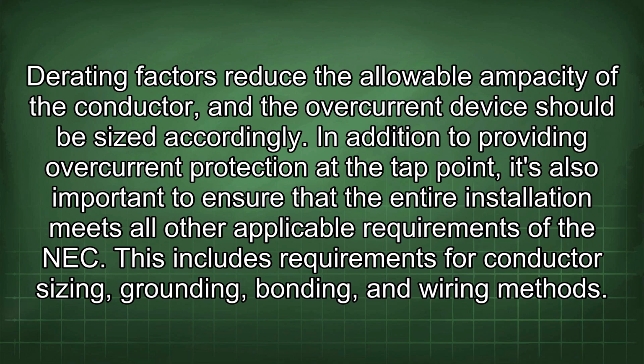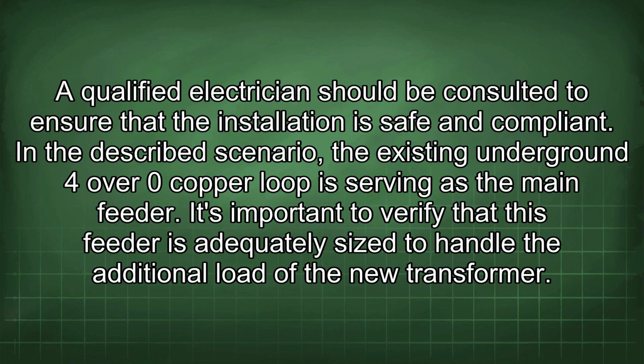In addition to providing overcurrent protection at the tap point, it's also important to ensure that the entire installation meets all other applicable requirements of the NEC. This includes requirements for conductor sizing, grounding, bonding, and wiring methods. A qualified electrician should be consulted to ensure that the installation is safe and compliant.